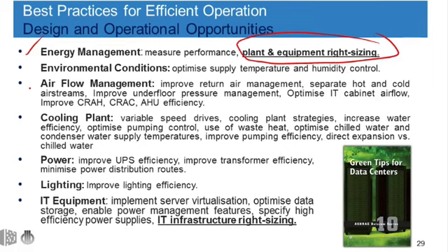They're being written into lease agreements now, and people are understanding what that means for them technically and commercially. Airflow management. There are a number of areas here. Many people concentrate on the supply air to the servers and IT equipment, which is very important. But equally as important is to ensure that you've got a good return air path back to the cooling system, whether that be CRAHs, CRACs, or air handling units.